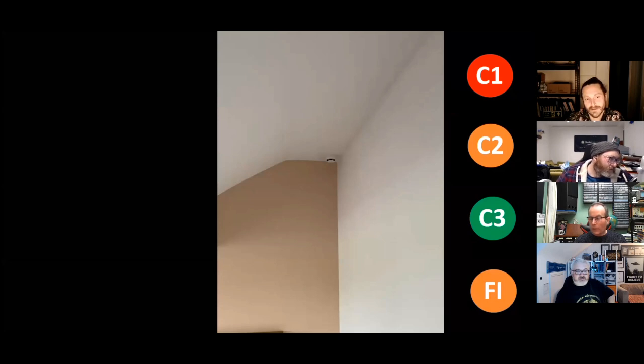Right, so we're going to share the results, and the results are in. 75% say it's a C1, 21% say C2, 0 C3s, and 4% FI. Well, I'm going to go to C1 because where it is, it's not going to work. You're not going to get the smoke even in it, so it's not going to actually do anything.